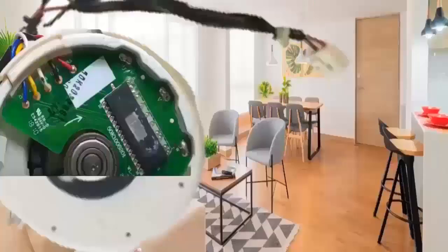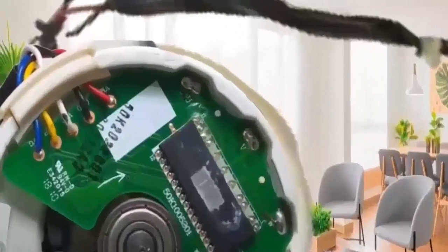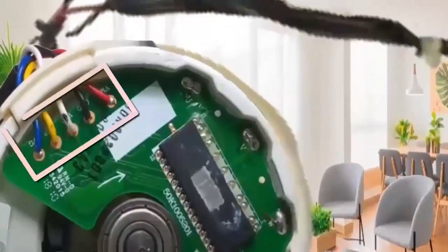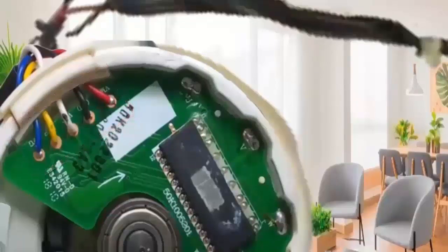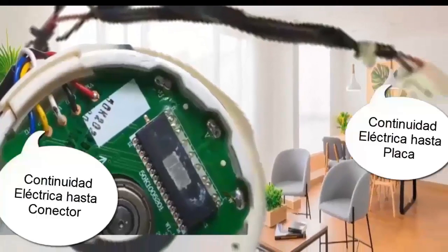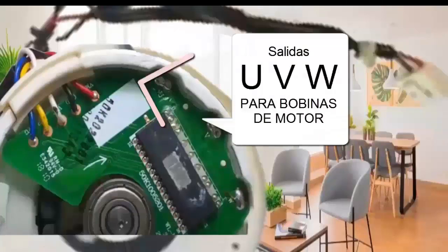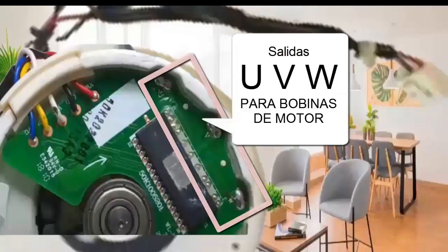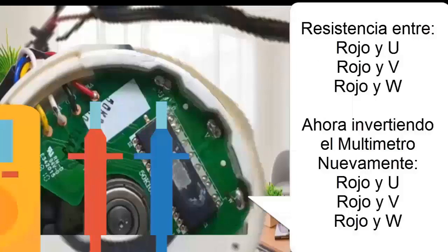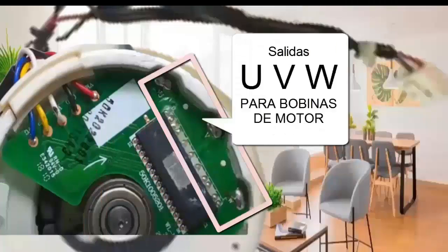4. If all the previous tests are passed, it is recommended to check for obstructions and ensure the motor spins freely when disconnected to rule out mechanical issues. 5. You can remove the fan motor, open its casing, and check if the power supply is effectively reaching the inside of the motor. Visually inspect the internal electronic board of the BLDC motor for anomalies and verify the continuity of all wires from the fan connector to the entry of the motor's electronic board.